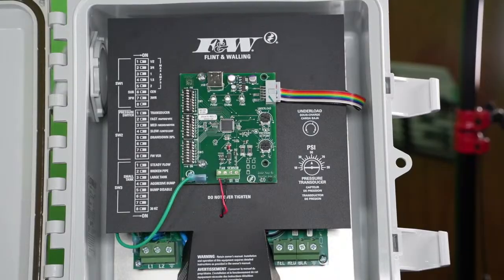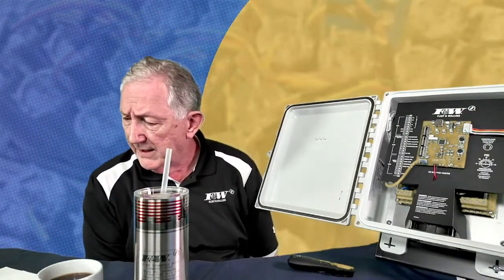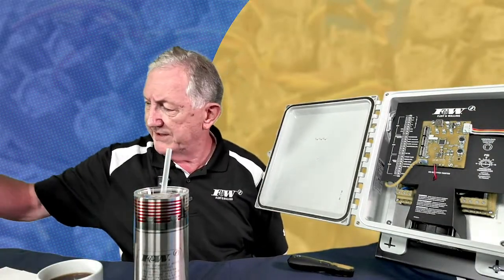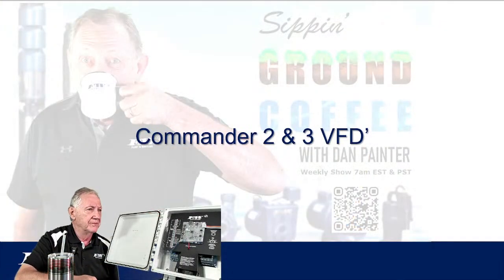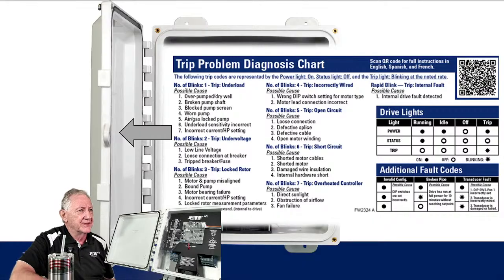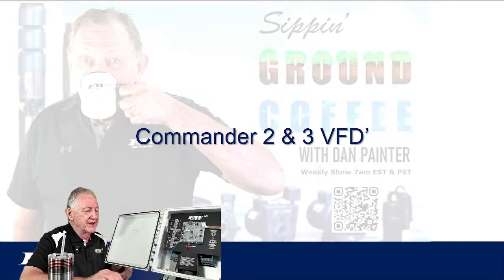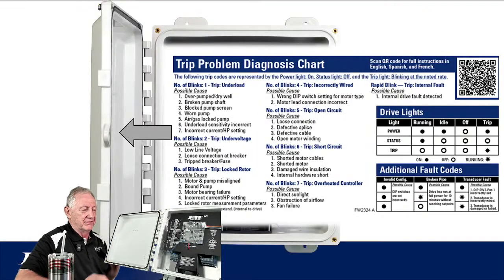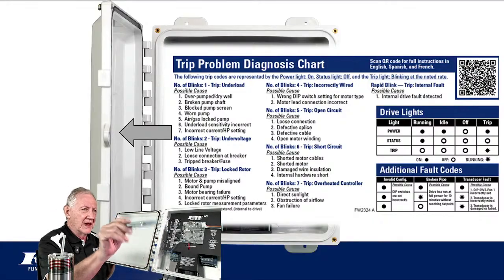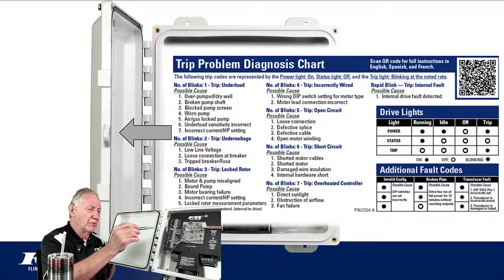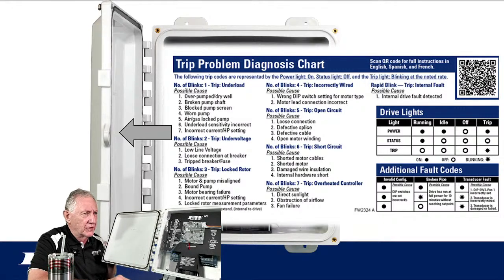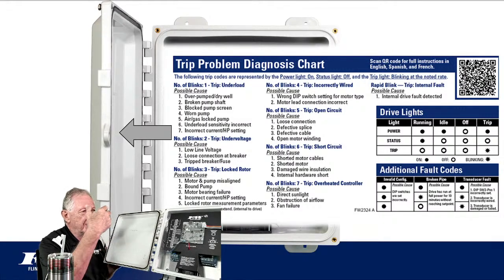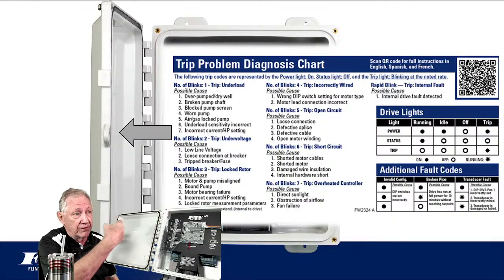So, as far as wiring this drive up, that really is not any different than wiring up a control box. I'm going to move to a slide now, Renee, and see if this works. Okay, so inside this control box, when we're referencing those indicator lights on the outside, this label that you see up on your screen will be put on the inside cover of the control panel. And what that label is going to do is tell us what the lights are indicating.